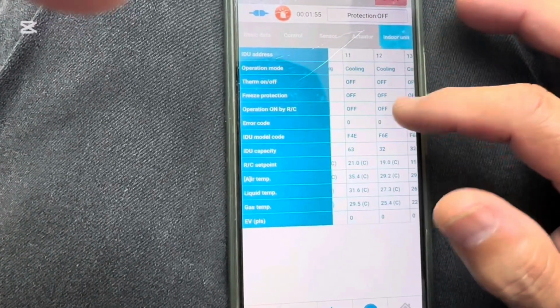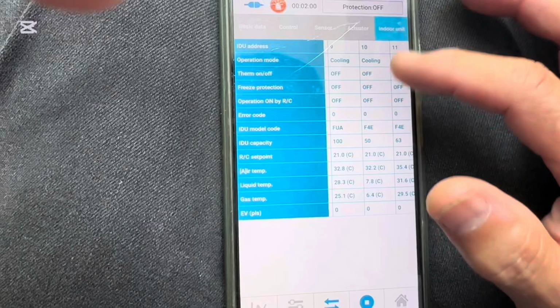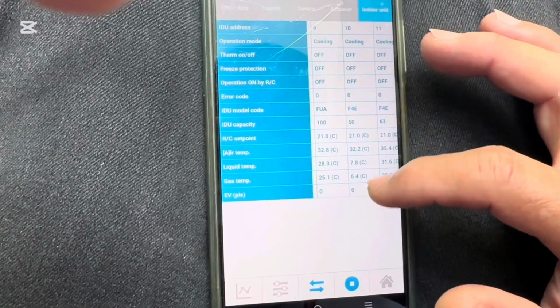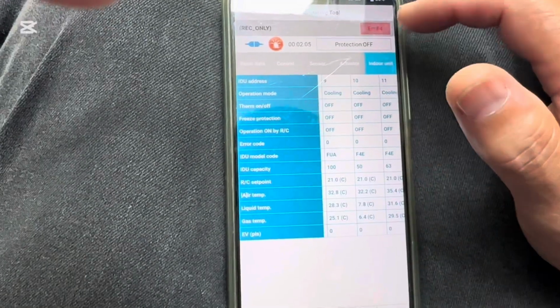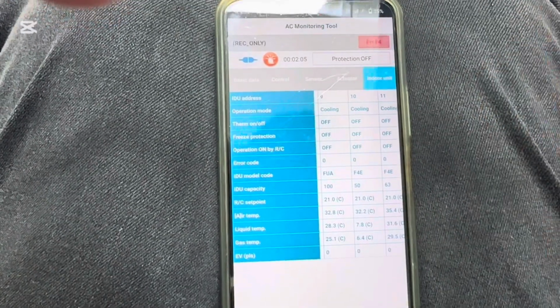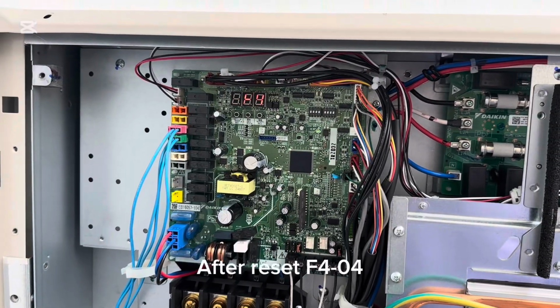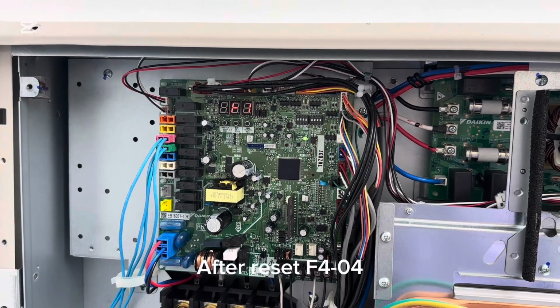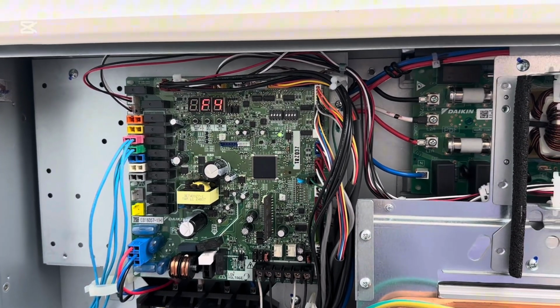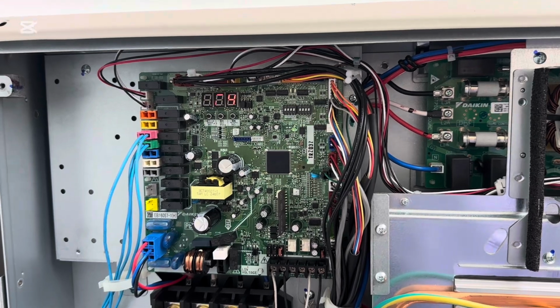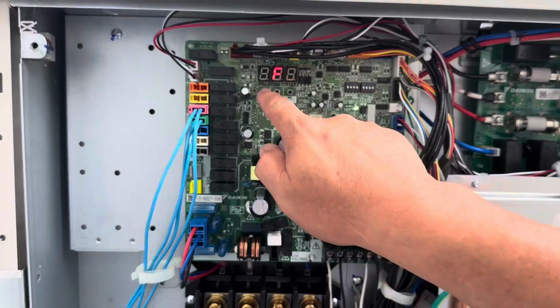We look again at unit number 10. Okay, the reading is very low. Aircon is off. This causes error code F4. F4-04. Why F4-02? Now it is F4-04. Okay, we check the history.